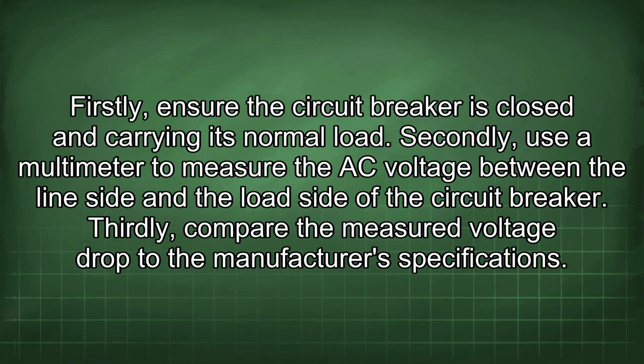Firstly, ensure the circuit breaker is closed and carrying its normal load. Secondly, use a multimeter to measure the AC voltage between the line side and the load side of the circuit breaker. Thirdly, compare the measured voltage drop to the manufacturer's specifications.